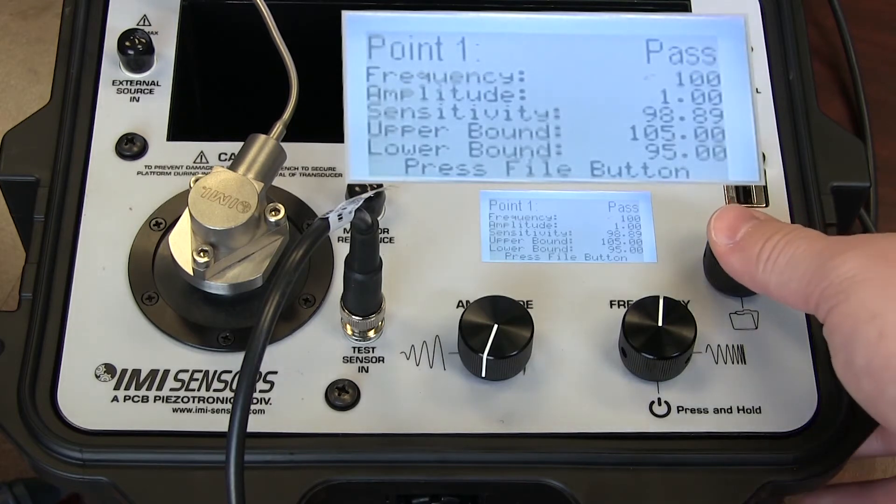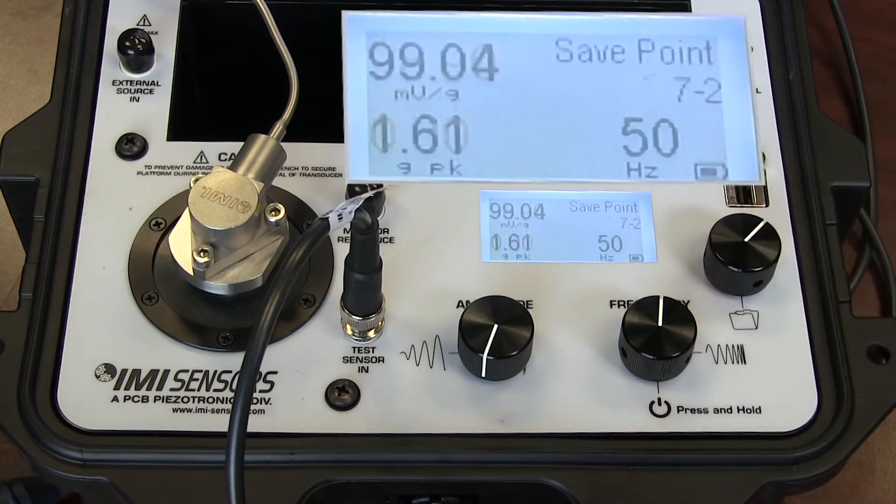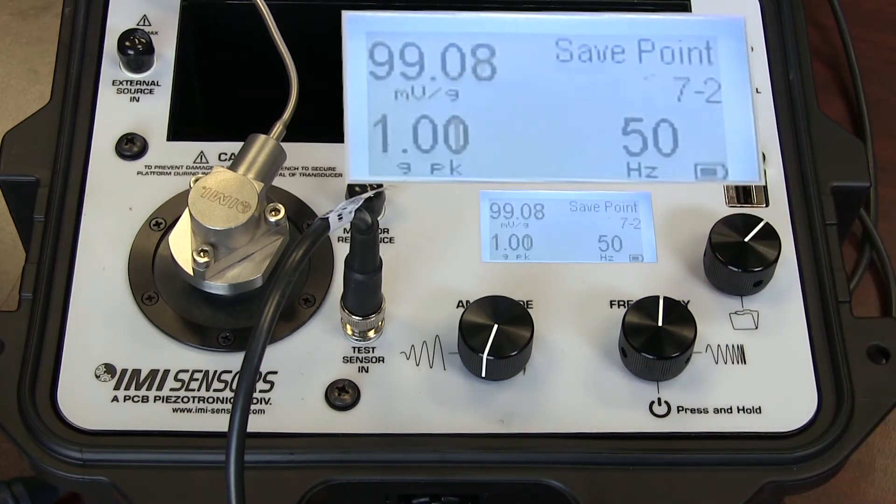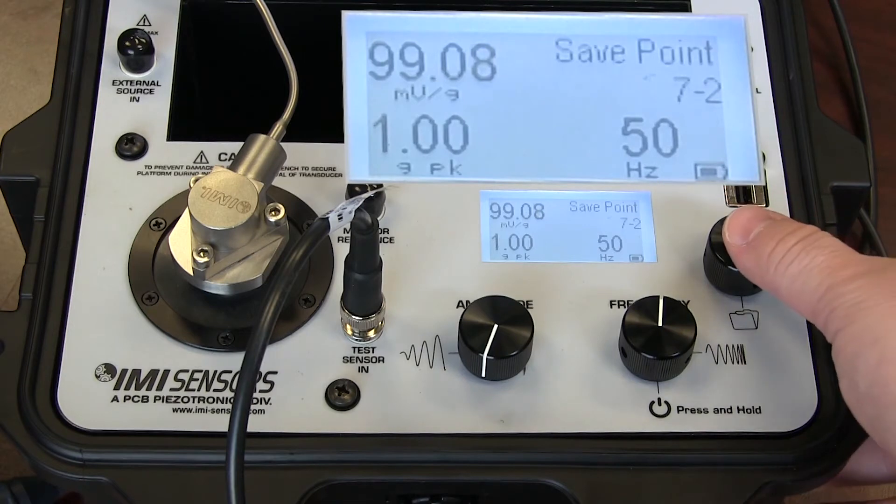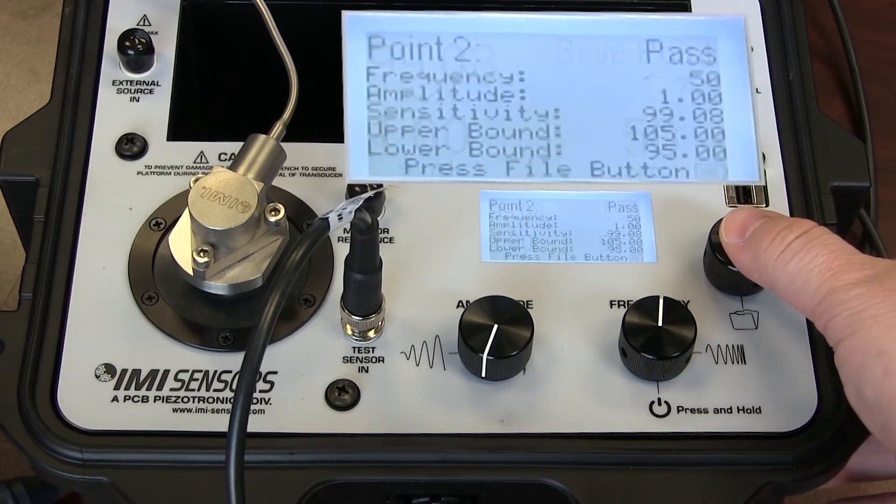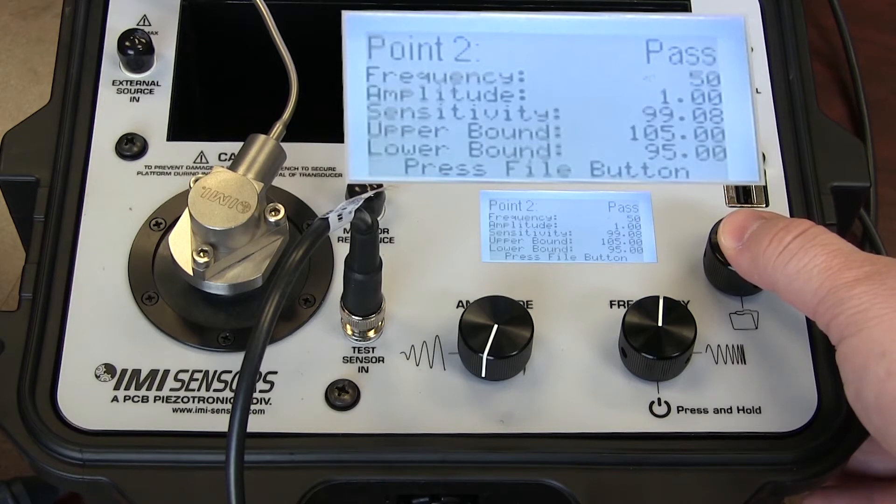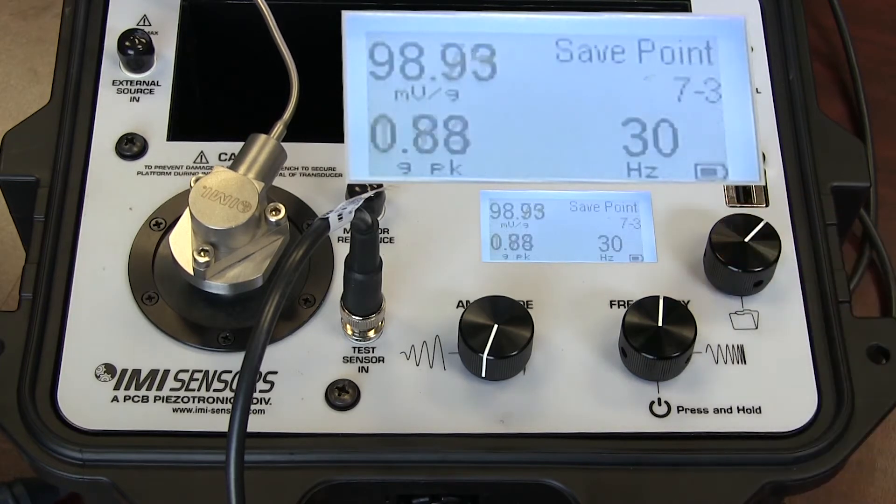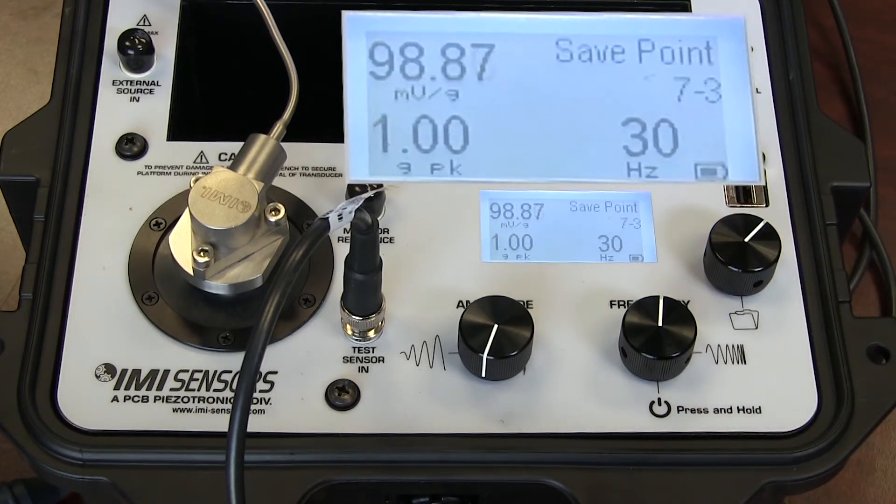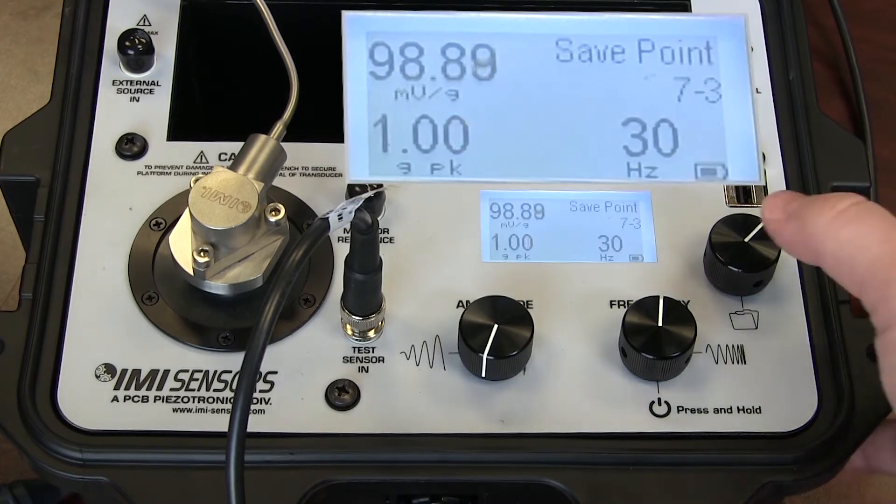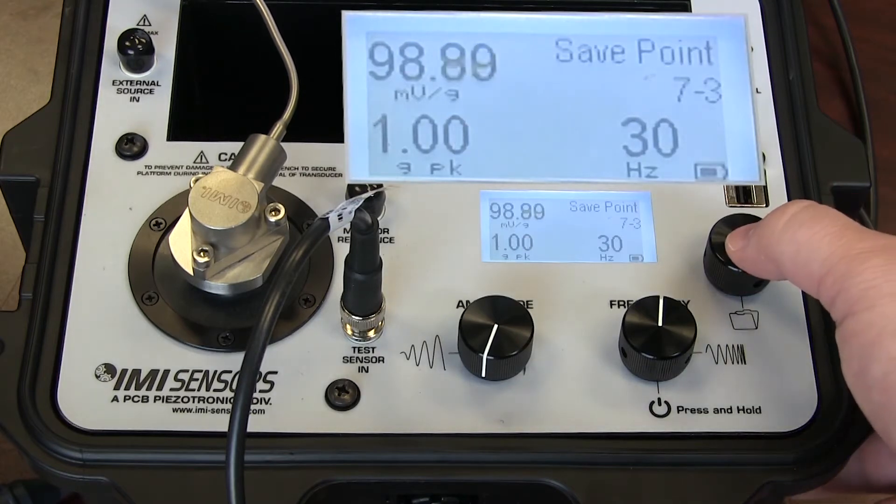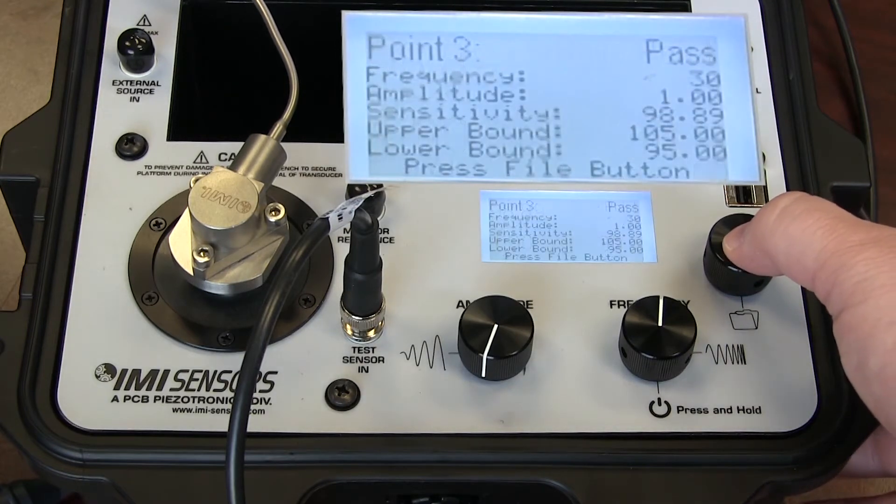If I press file again, we go to the next test point, which is 50 Hz at 1G peak. And you can see I'm still at 99 mV per G. If I press file again, it tells me that I once again pass. The next test point is 30 Hz. Now you can see I'm moving relatively quickly. I give it a moment to settle. The shaker is at, once again, I pass.